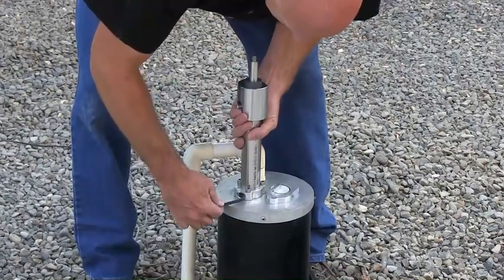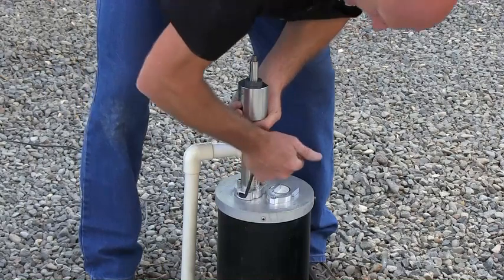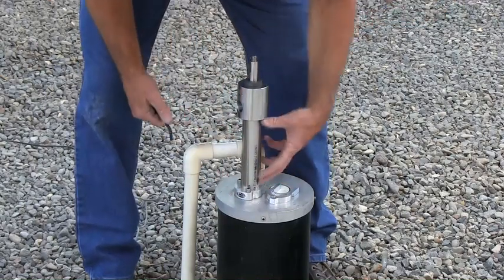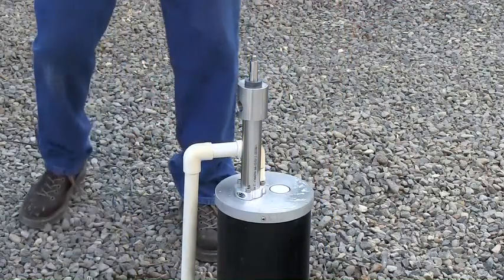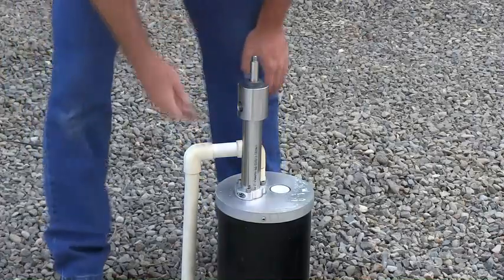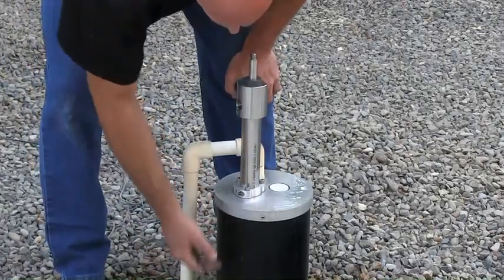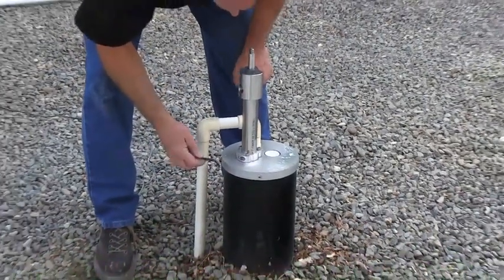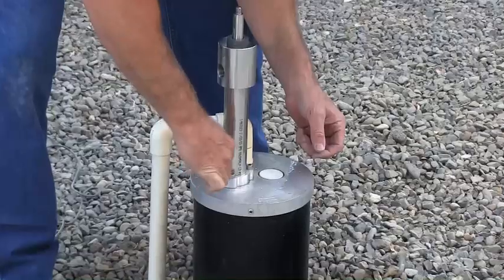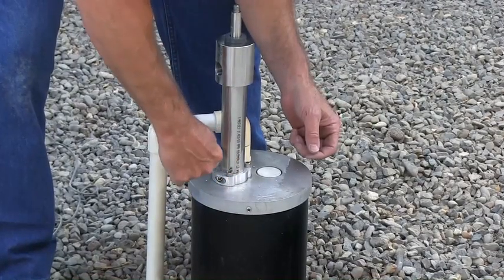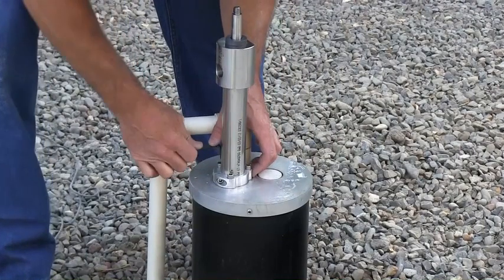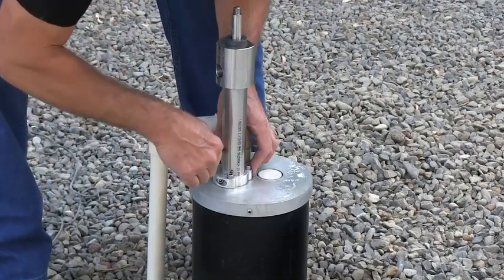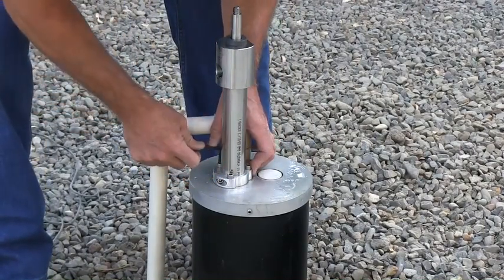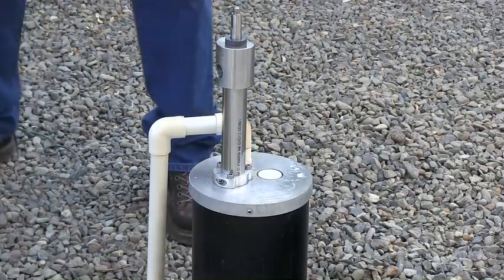We're going to tighten up the pinch bolt on the split flange. In this particular case, we don't need a whole lot of simple pump riser tube above the well cap because our well cap protrudes about 16 or so inches. Tightening down the 3 mounting bolts on the split flange.